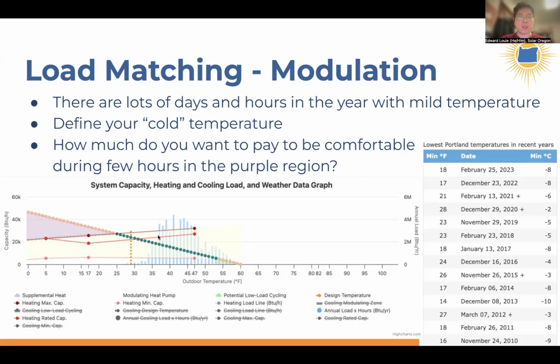So this graphic is an example from Portland, Oregon. The blue columns show what's called the load times the hours. Basically, we're talking about the number of hours in the year when the outdoor temperature is 50 degrees, for example, or 40 degrees. Those hours are then multiplied by the heating requirement to keep this home comfortable when it's 40 degrees outside. That multiplication results in those blue columns, and for the most comfort, the goal is that your heat pump has a modulation range that covers most of the blue area.